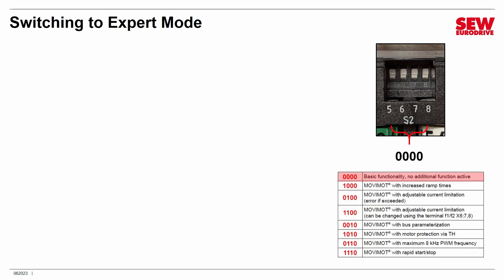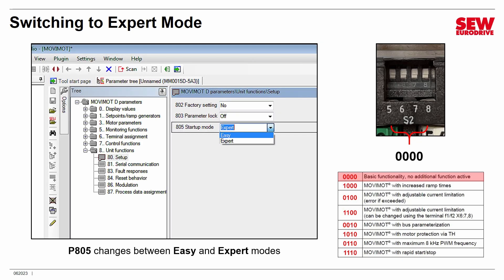How do you switch to Expert Mode? It's relatively simple. First, make sure your DIP switch bank S2, switches 5 through 8, are set to all zeros — the basic functionality mode. If your Movimot control head switches are set to an alternative behavior, change them back to all zeros before switching to Expert Mode. Once done and the Movimot is powered up, connect to your PC using a USB interface, start Movitools Motion Studio, scan in, then go to parameter 805, change it from easy to expert. That's all.